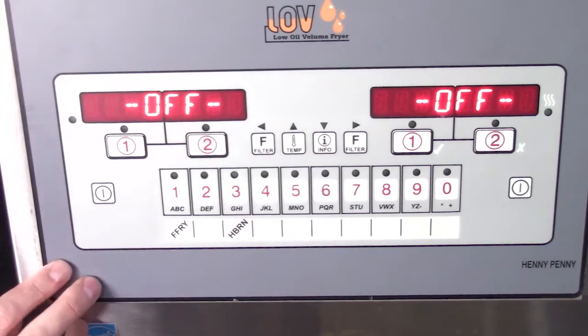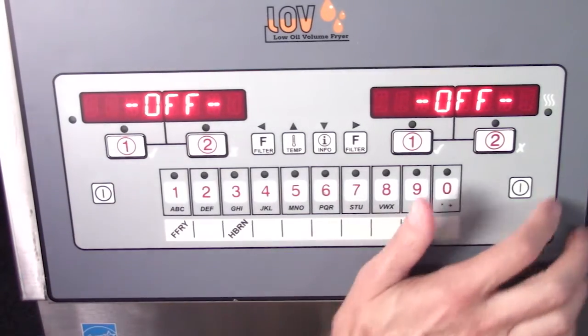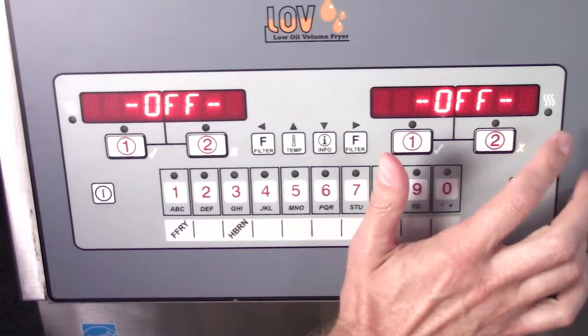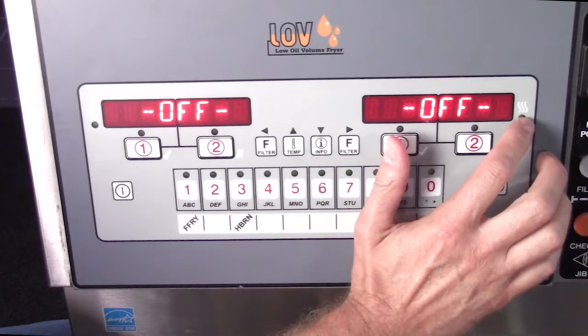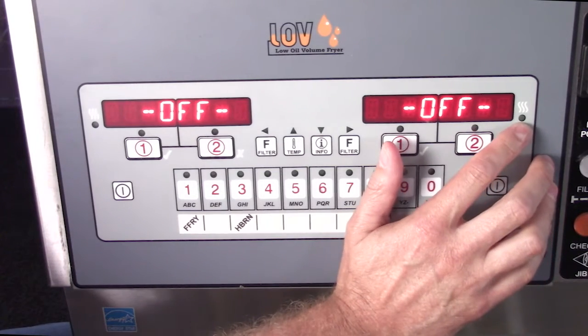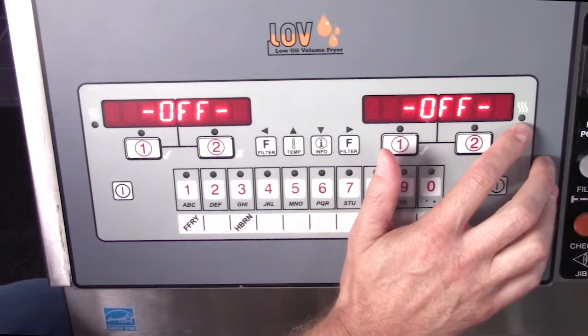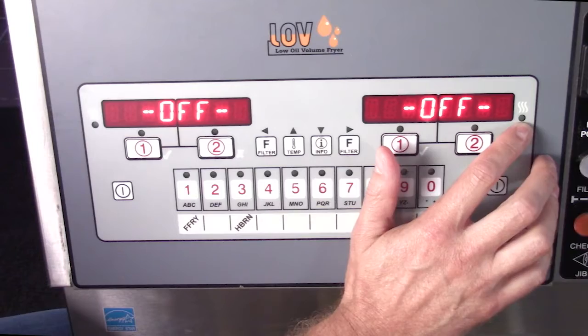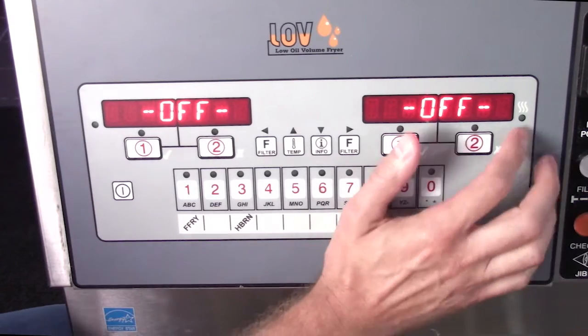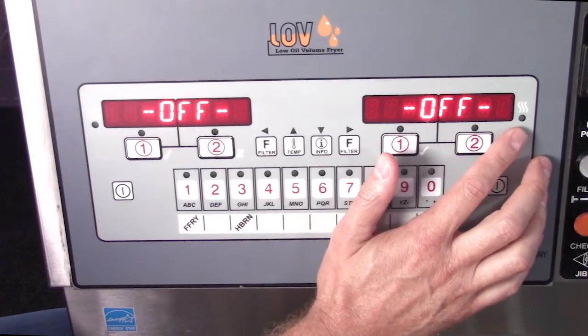That way it's not too noisy as I'm speaking. So you want to watch the heat light. When I turn the unit on, the heat light should be kind of pulsing slowly. That's because it's waiting for our fan or our blower motor in the back to get up to the RPMs to close the pressure switch to go ahead and start our heat sequence.